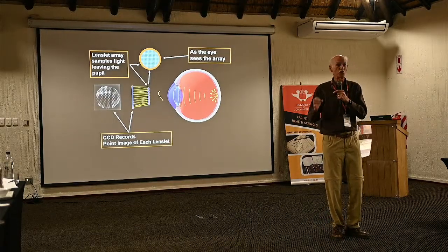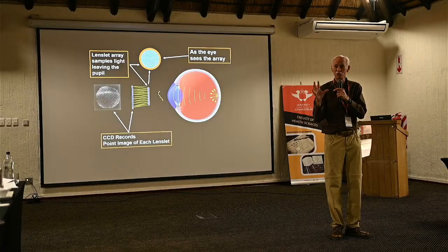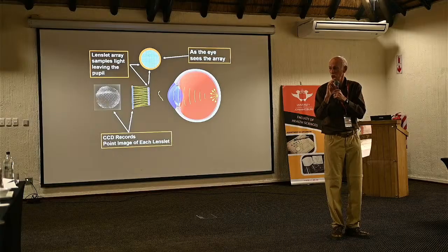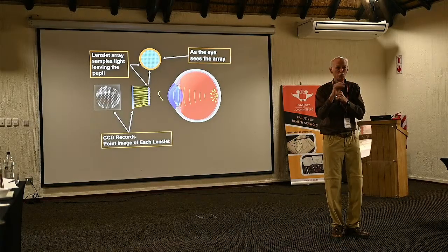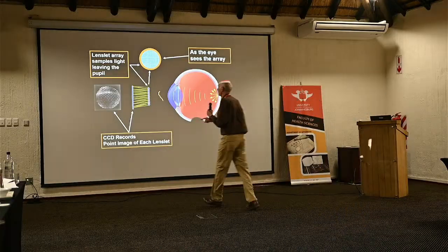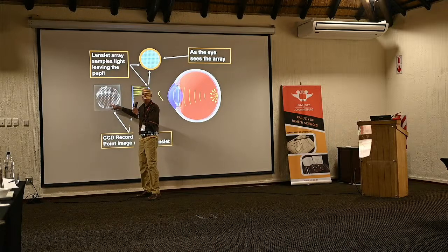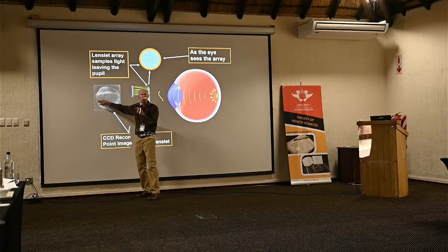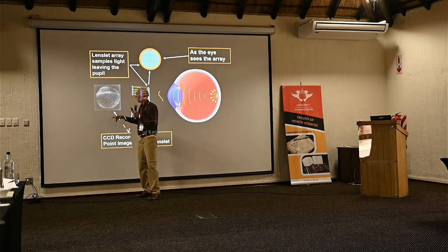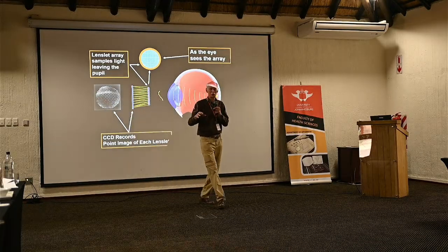Couple ways to handle that. One is you might shrink the analysis pupil down. They often have a command on the instrument. It says, where would you like the analysis pupil to be? And we'll just get rid of all the other dots, just center on maybe just this little piece right there. Say, I can get a circle in there. Let's use that one. You know, you might choose to do that. But then you're ignoring these data up there, and those data too, they count. For vision, they'll count. See? Or another way to deal with it is to have a second camera that actually takes a picture of the pupil.